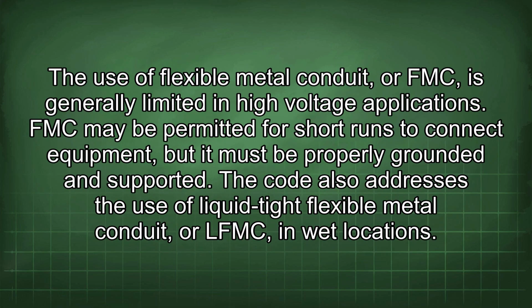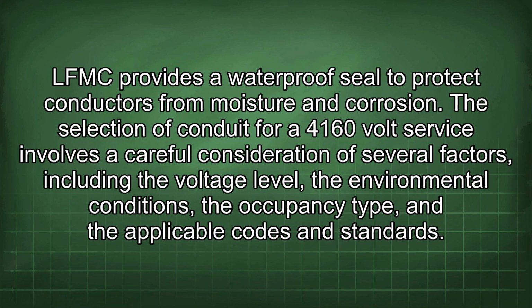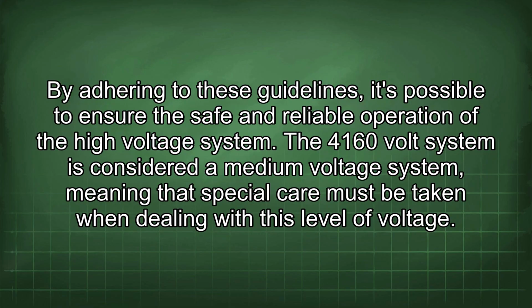situation. The use of flexible metal conduit, or FMC, is generally limited in high-voltage applications. FMC may be permitted for short runs to connect equipment, but it must be properly grounded and supported. The code also addresses the use of liquid-tight flexible metal conduit, or LFMC, in wet locations. LFMC provides a waterproof seal to protect conductors from moisture and corrosion. This selection of conduit for a 4160-volt service involves a careful consideration of several factors, including the voltage level, the environmental conditions, the occupancy type, and the applicable codes and standards. By adhering to these guidelines, it's possible to ensure the safe and reliable operation of the high-voltage system.